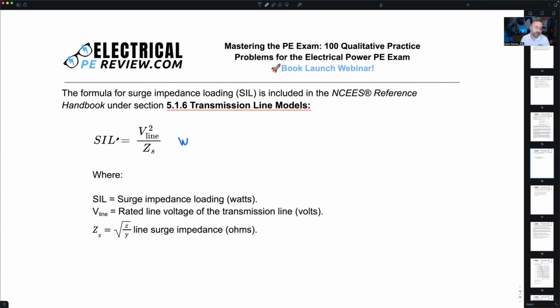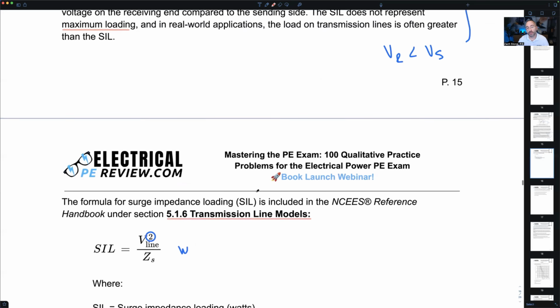However, we can solve for the surge impedance loading using the S equals V squared over Z formula, where we take the square of the transmission line voltage and we divide it by a special impedance known as the line surge impedance. This formula is also in the reference handbook in the same section. The surge impedance is equal to the square root of the ratio of our series transmission line impedance divided by our total shunt admittance.